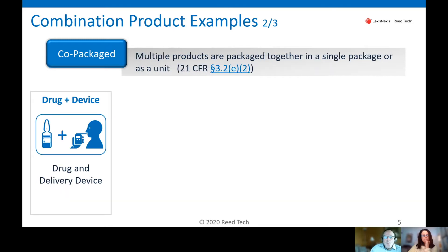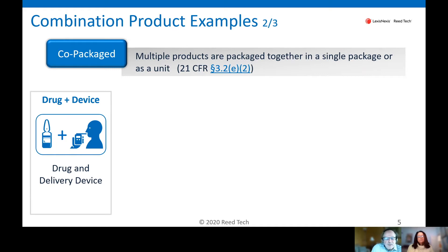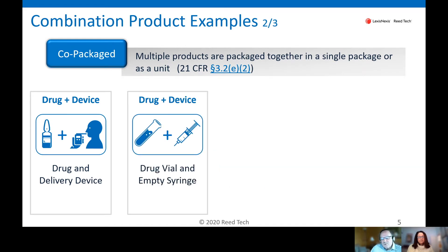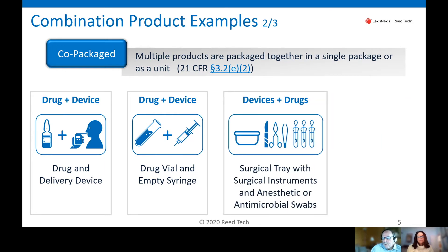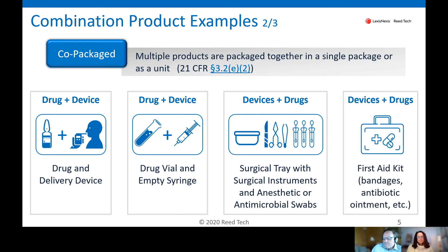Let's move over to co-packaged examples. In this case, we have multiple products — a device and a drug — packaged together, but you can identify the individual components. A common example might be a drug and a delivery device, such as an inhaler where you place a capsule, assemble it, and apply the drug to the patient. Another common example is a drug vial with an empty syringe. Surgical trays with drug components would be another example, and a first aid kit containing devices such as bandages and drugs like antibiotic ointment.